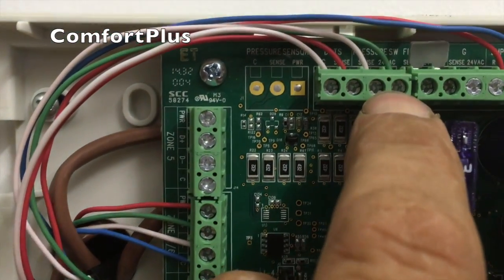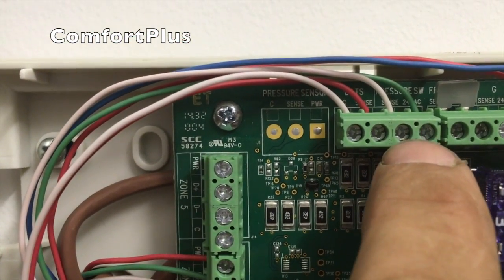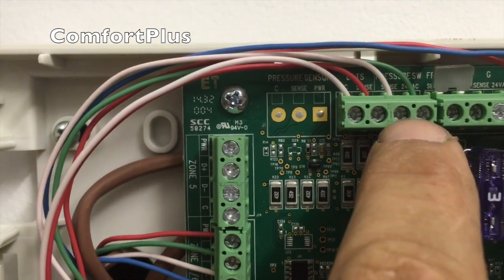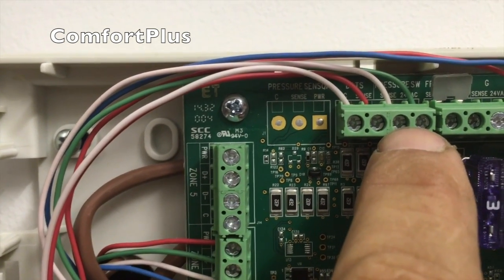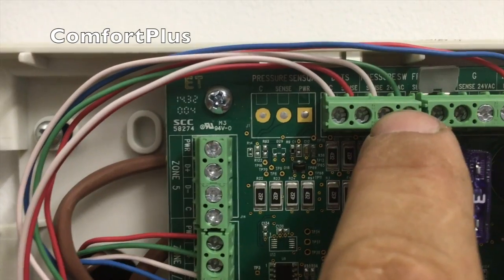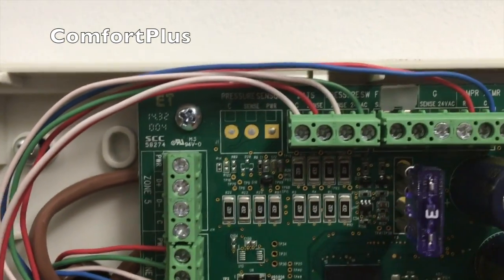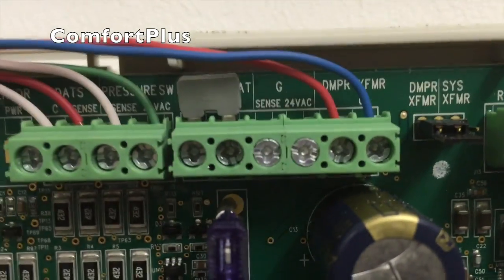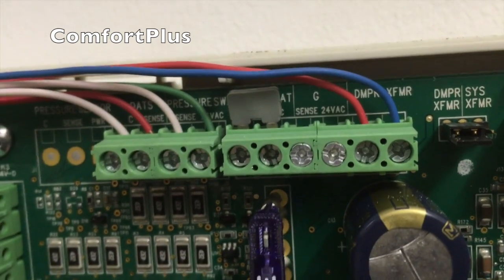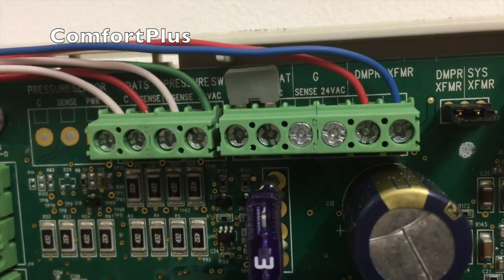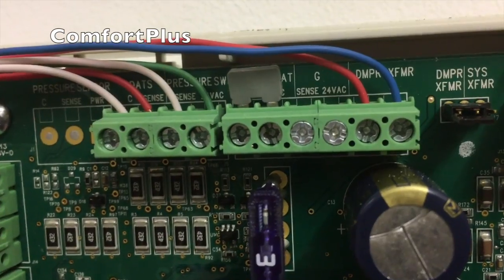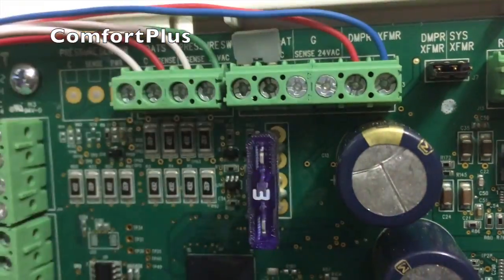I brought a 4-conductor cable up from the air handler here. 2 of the wires is for my pressure switch that I put on down there for heat pump operation. Wants to make sure that it doesn't close off too many zones when it's heating and build up the pressure too high. And then the other 2 wires in that cable are for the additional 24-volt transformer I installed in the air handler to run the control panel and the dampers themselves.